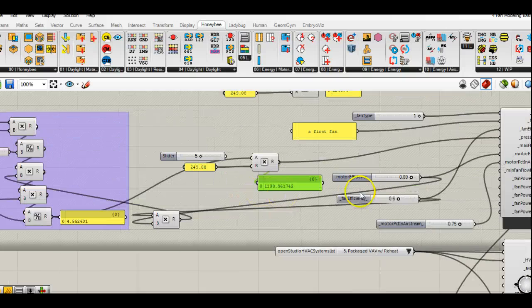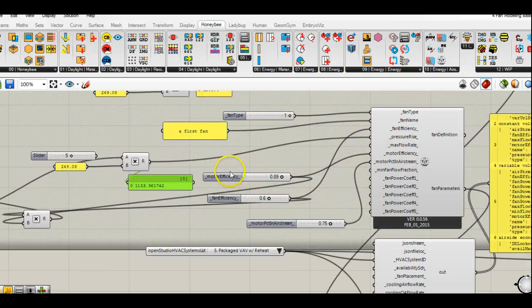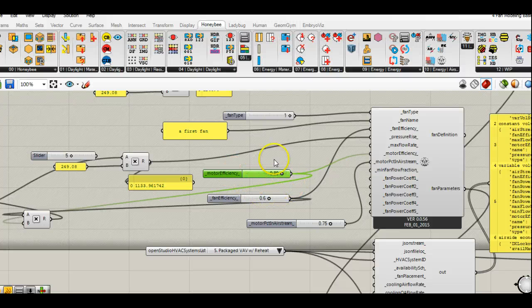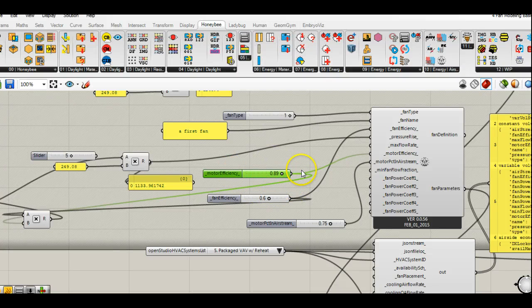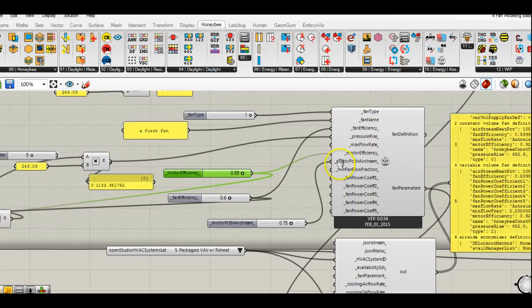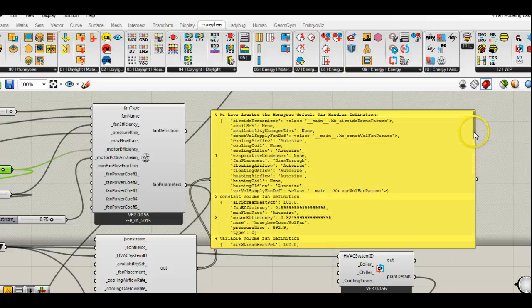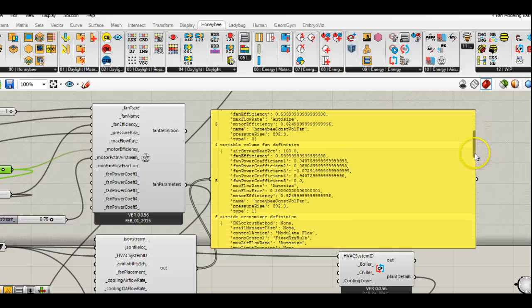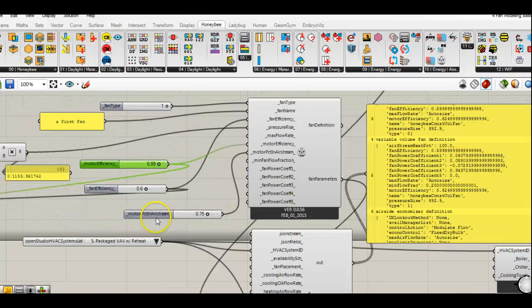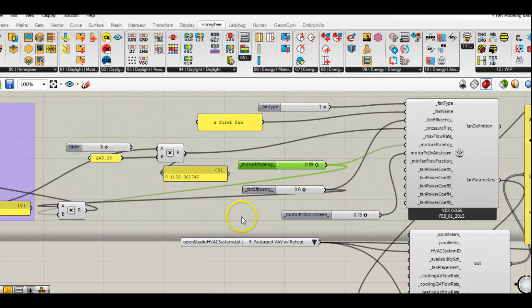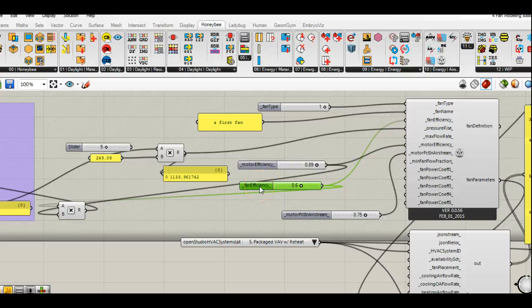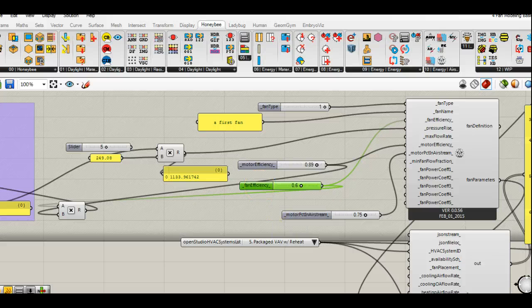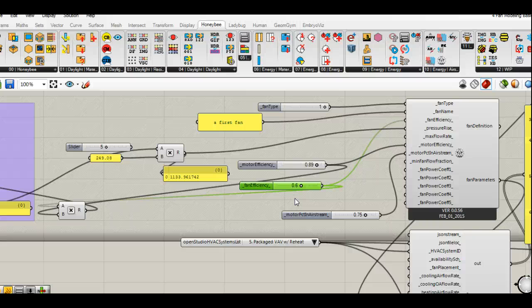The motor efficiency and fan efficiency, you can look at the Honeybee defaults here. They're not too bad: fan efficiency of 60 percent, motor efficiency at 82.5 percent as a default. The motor efficiency is a little low. The fan efficiency, just so you're aware for the engineers, includes all mechanical losses, so not just the loss of the blades of the fan but also shafts and that sort of thing.